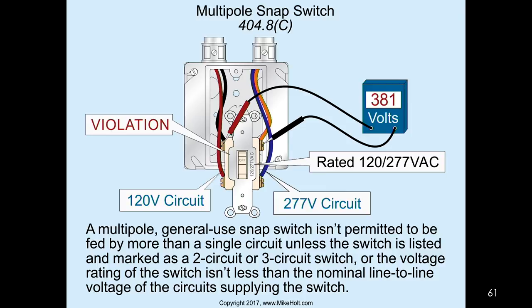Multi-pole snap switches. Now let me just kind of describe what this is here. We have a 120 volt circuit, and this red is the switch leg here, and then a 277 volt circuit, and we're switching this, and the purple is going to be my switch leg. You say, well, why would you switch 120 and 277 on the same switch? Brian, you want to give us some examples, and I've done this when I was a contractor. Well, there's a lot of reasons why you would want to, but the one that's probably the most common is in restroom areas. You'll have a men's and women's bathroom sharing a single exhaust fan, but you want the lights to be switched separately.